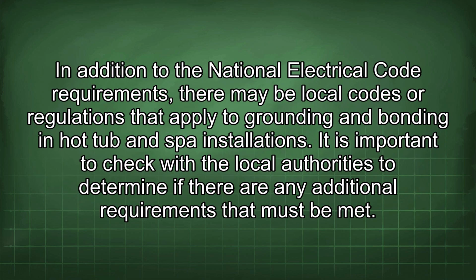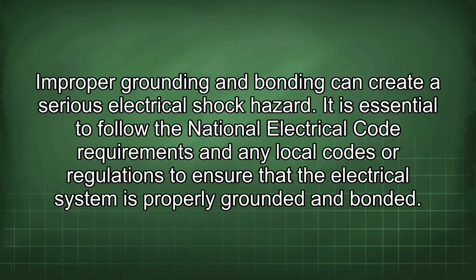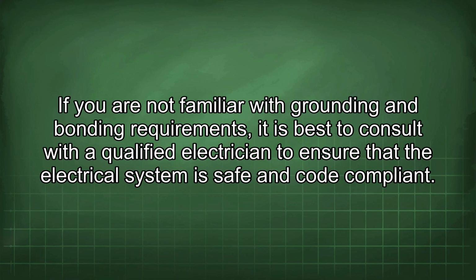In addition to the National Electrical Code requirements, there may be local codes or regulations that apply to grounding and bonding in hot tub and spa installations. It is important to check with the local authorities to determine if there are any additional requirements that must be met. Improper grounding and bonding can create a serious electrical shock hazard. It is essential to follow the National Electrical Code requirements and any local codes or regulations to ensure that the electrical system is properly grounded and bonded. If you are not familiar with grounding and bonding requirements, it is best to consult with a qualified electrician to ensure that the electrical system is safe and code compliant.